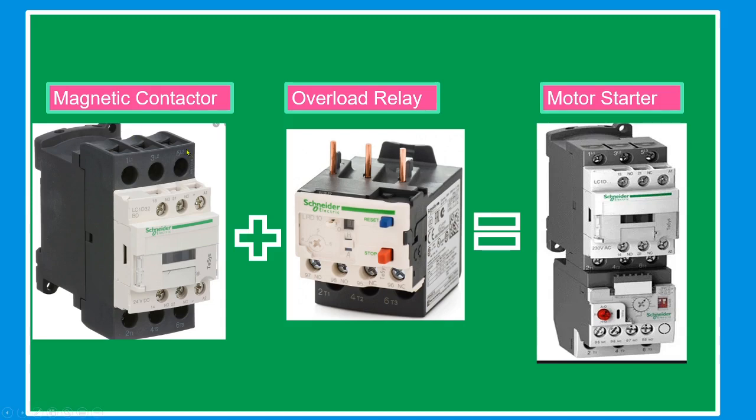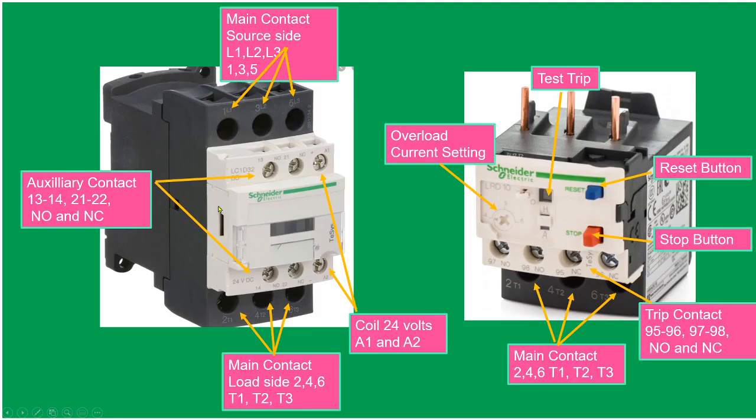Now this is the magnetic contactor. This is the overload relay, and this is the compact motor starter. This is the magnetic contactor: line one, line two, line three. The main contact source is line one, line two, line three, or one, three, five. On the other side, it's also main contact, but this one is the load side: two, four, six, or T1, T2, T3.